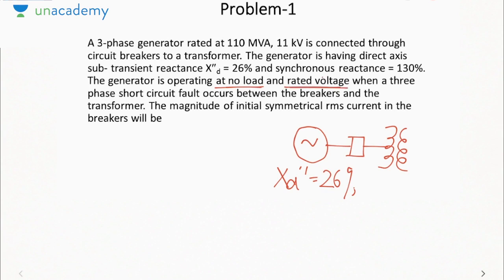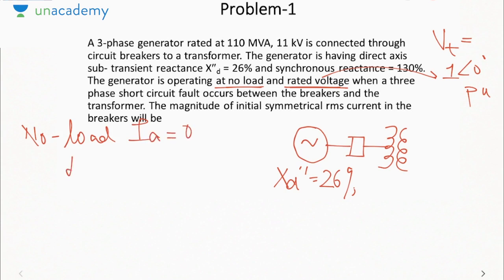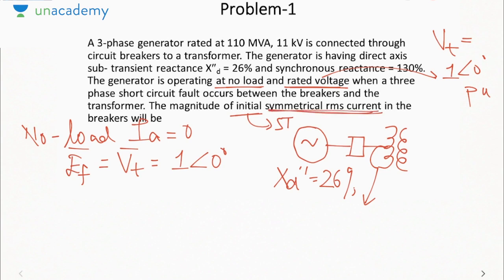What does the rated voltage signify here? That the voltage is 1 angle 0 degree pu. This is your VT, and due to no load, IA is 0, so EF will be equal to VT, which will be equal to 1 angle 0. When a three-phase short circuit fault occurs between the breaker and the transformer, we need to find the initial symmetrical RMS current in the breaker. Initial means subtransient. Symmetrical RMS current means only the AC component.